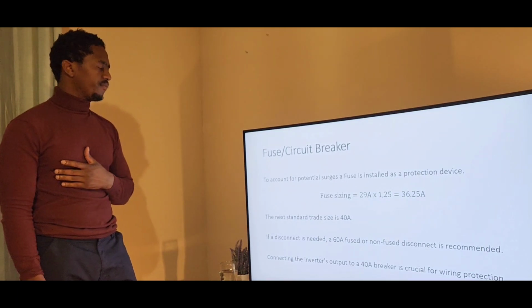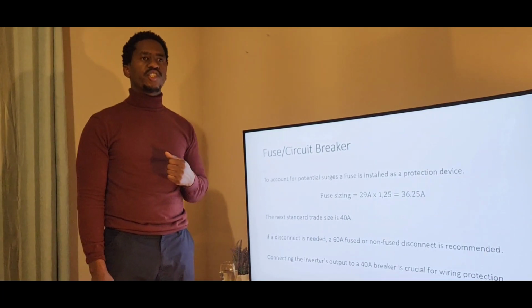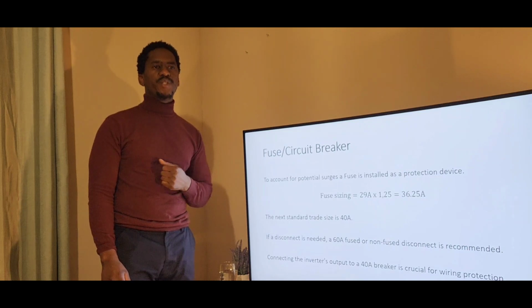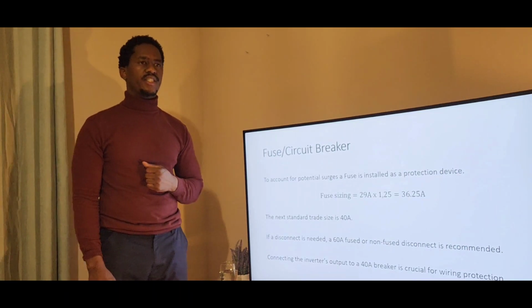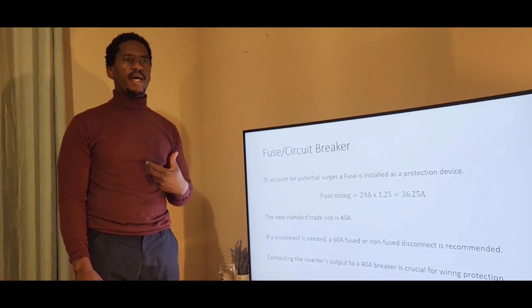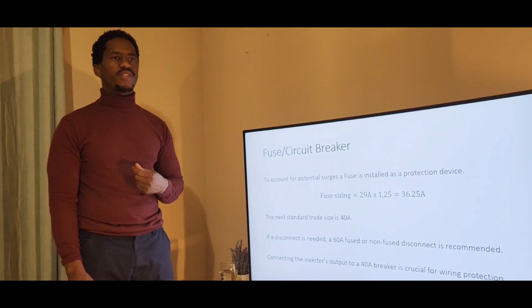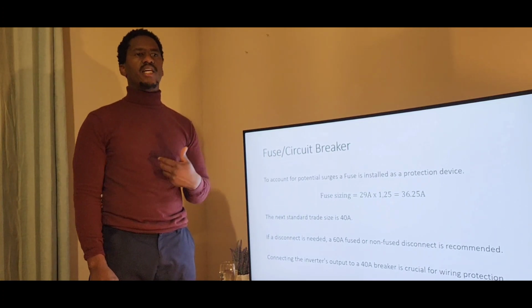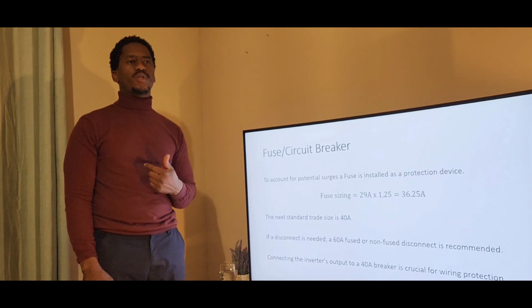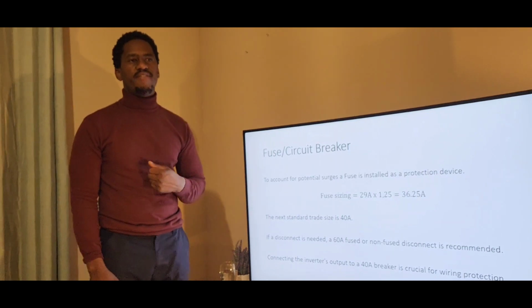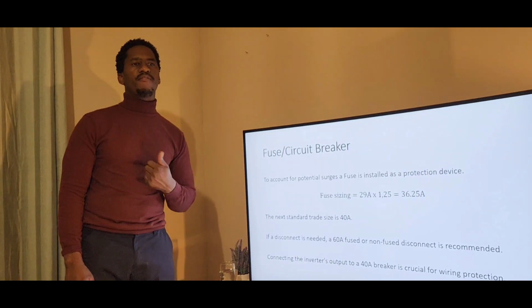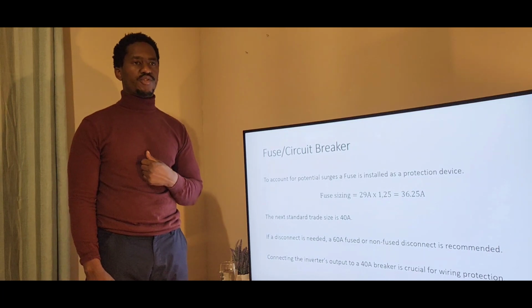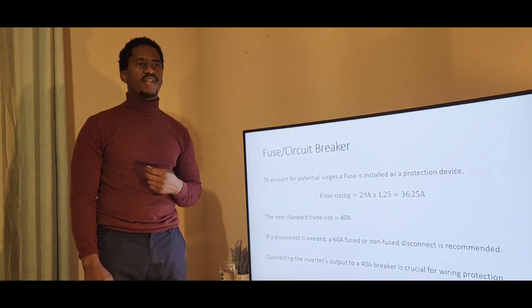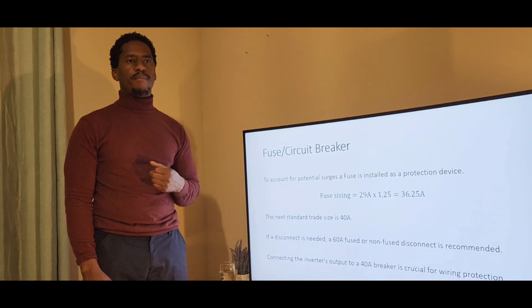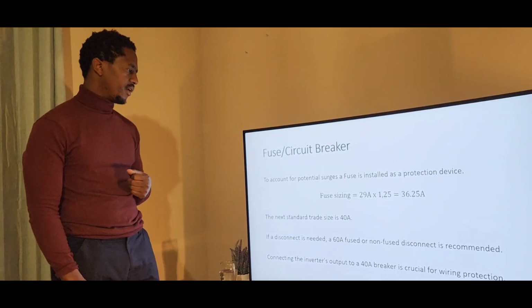Fuse or circuit breaker. To account for potential surge, a fuse is installed as a protection device. Fuse sizing: 29 amps by 1.25, which gives us 36.25. The next standard size fuse or circuit breaker would be 40 amps. If a disconnector is needed, a 60 amp fused or non-fused disconnector is recommended. Connecting the inverter output to a 40 amp breaker is crucial for wiring protection.